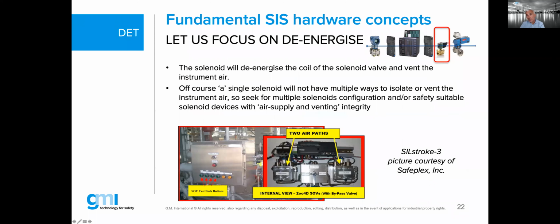Now, if you move from the relay into the solenoid itself, and I took here an example from the industry, you may think, well, that's a very complex replacement of one single solenoid. Well, you can already imagine the majority of all the failures in the industry are always here on the final elements. Without pointing a finger to the vendors of those types of material, it is purely based on practical experience and feedback from the industry that 50% of all the safety instrumented function failures are always here, those two final elements. Either the solenoid, or mainly the final element itself, being your fail to close or your fail to open valve.